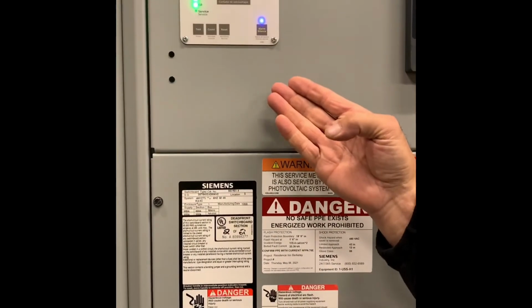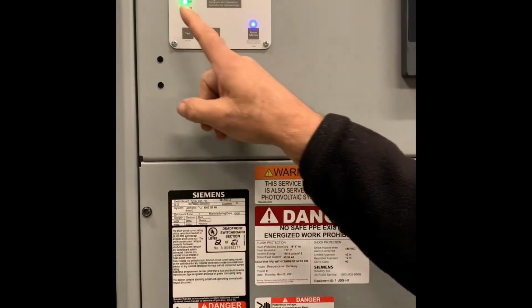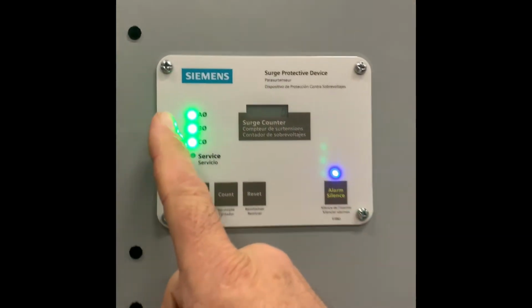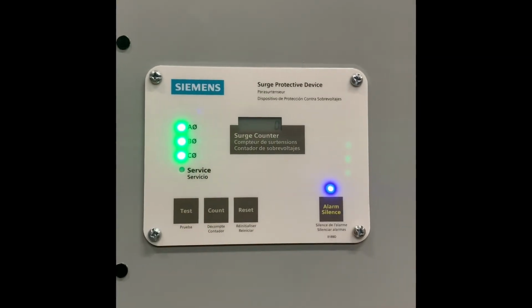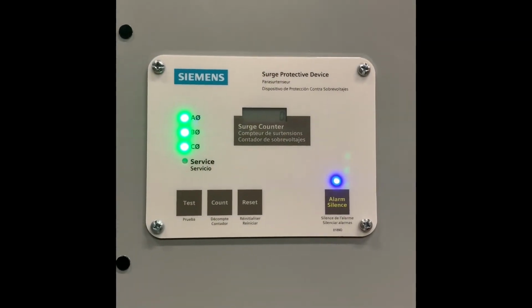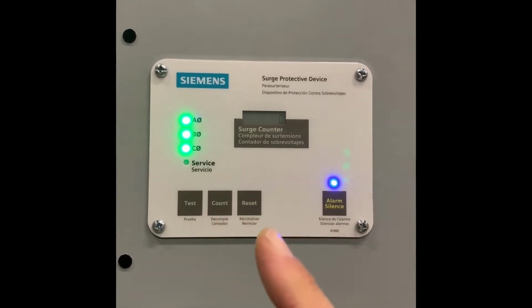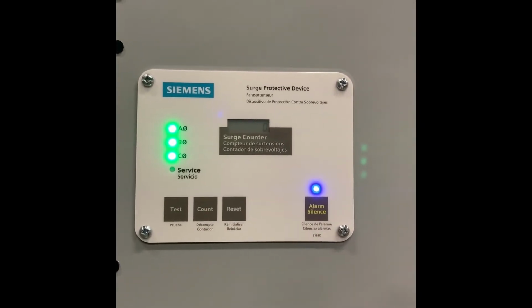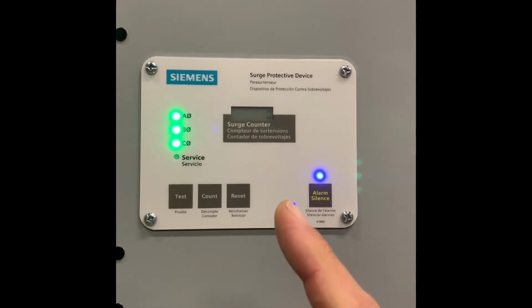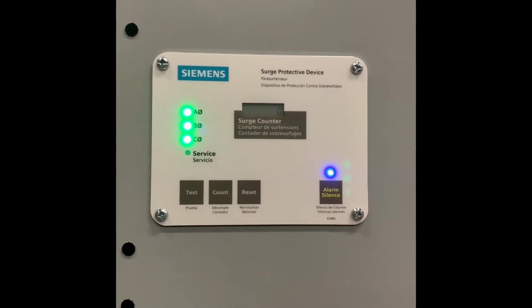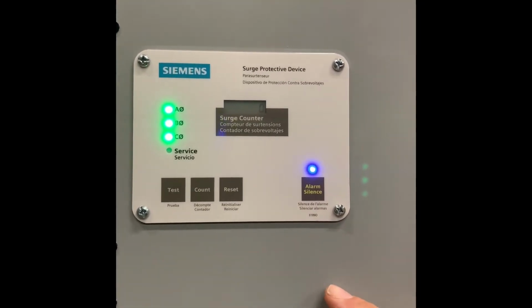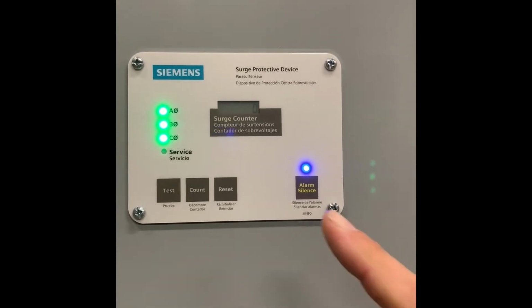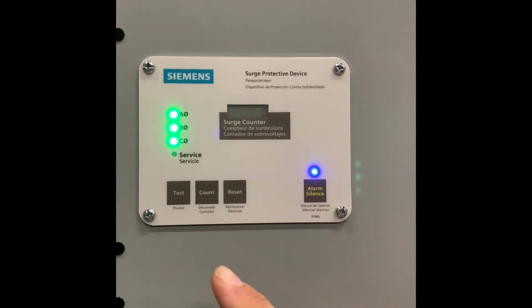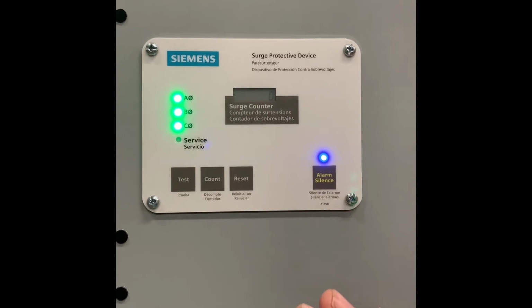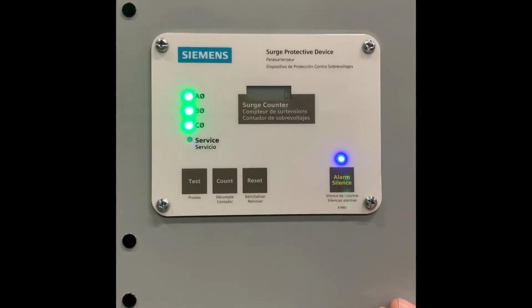This is a transient voltage surge suppression device. Currently there are 3 green lights. This is exactly what you want to see. They're dual mode, so when it changes to yellow, that means it's time to service it. When it changes to red, that means it is no longer protecting the system. We have a very good warranty on these. If they fail because they're doing their job, we'll replace it. Warranty terms and conditions are in the O&M manual.